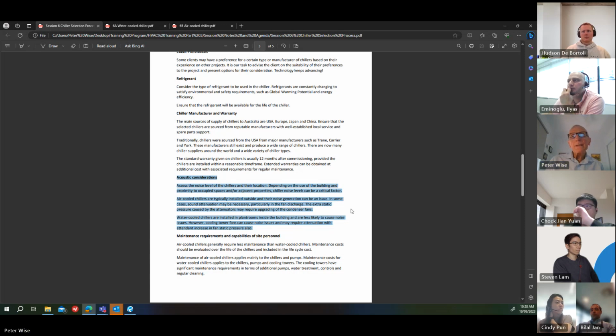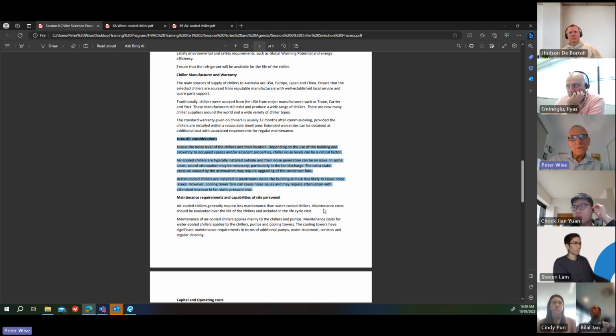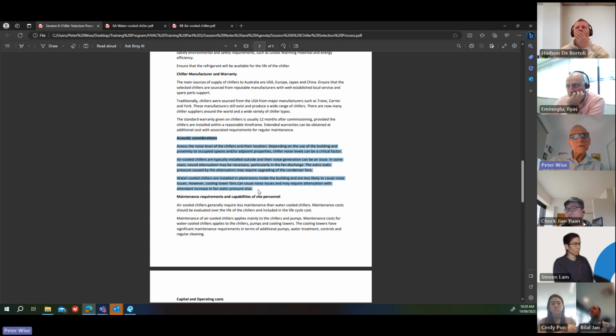This is not unusual. The standard air-cooled chiller might have a propeller type fan, which doesn't really have any external static available or any extra external static. It's been sized to draw the air through the condenser and discharge it, and that's it. If you're going to put an attenuator on, and if the chiller is installed in a plant room, for instance, or an enclosed area where you've got a resistance for the air to be drawn in, then there's extra static, and they probably have to put an axial fan on to get the extra static. And extra static means extra noise, so you've got to account for that.